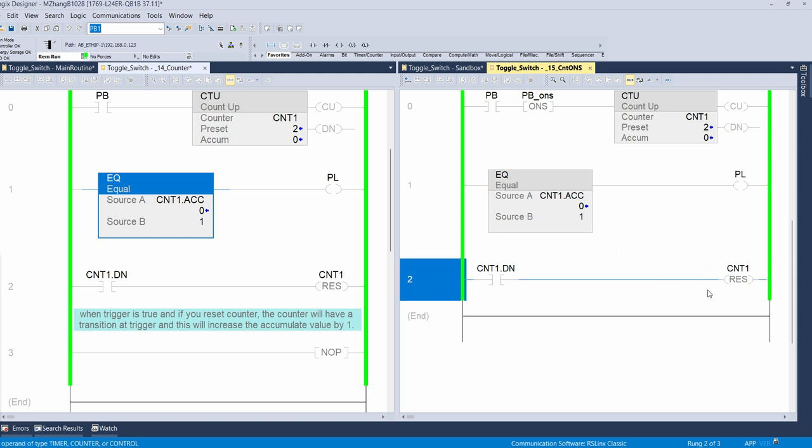So this is one thing we get familiar with: the counter instruction, the double integer instruction, and also reset. At the same time we find another application of the one shot. We put the one shot over here, and you understand the reason behind it. It's not because the counter doesn't have a one shot function built in. It has, but now we want to use the one shot to guarantee that it won't be affected by the reset, because you then automatically reset the counter. Okay.